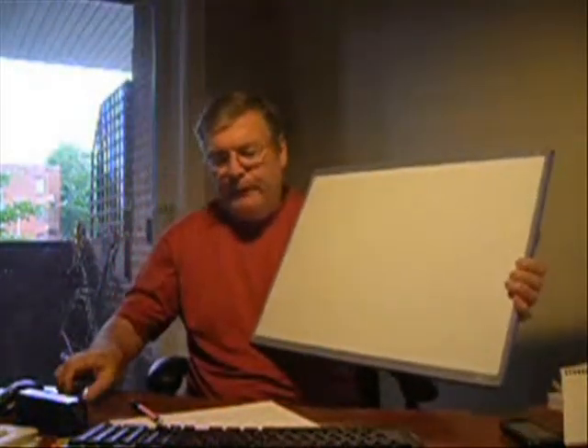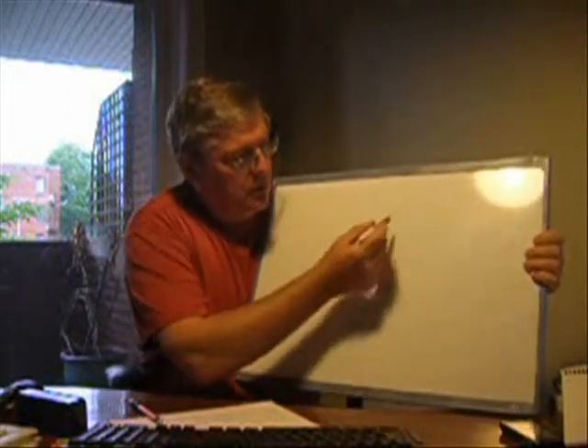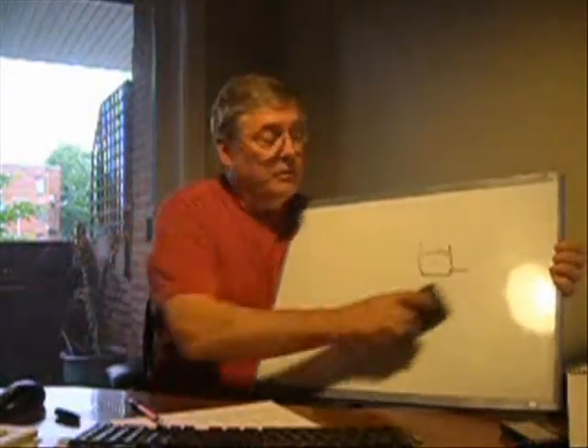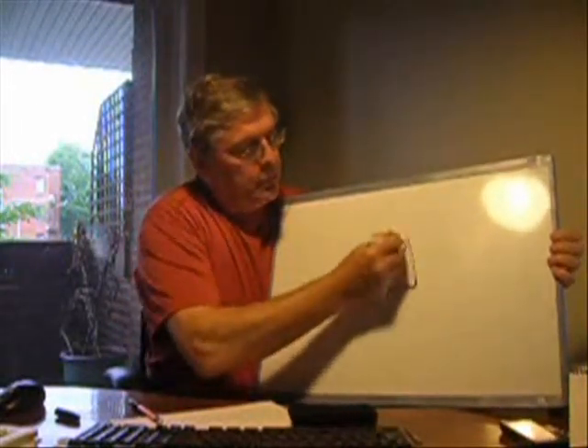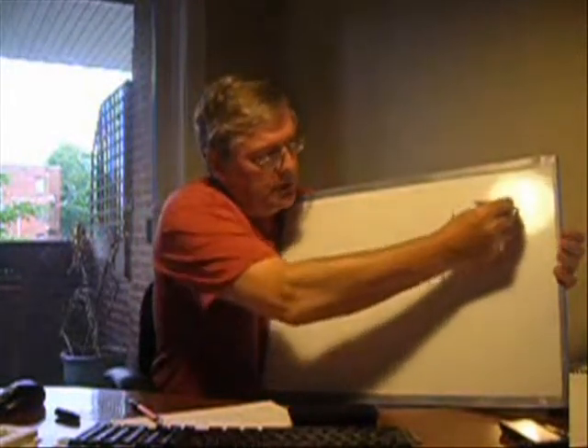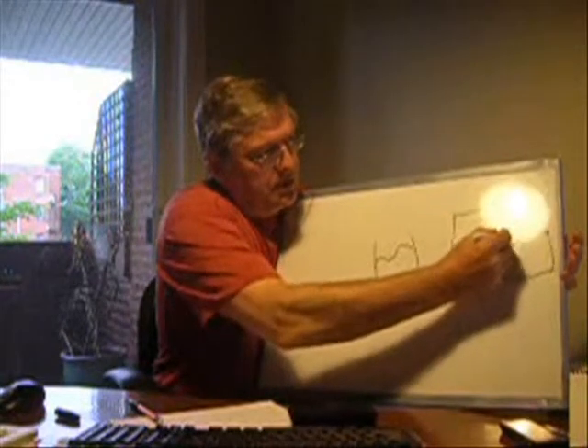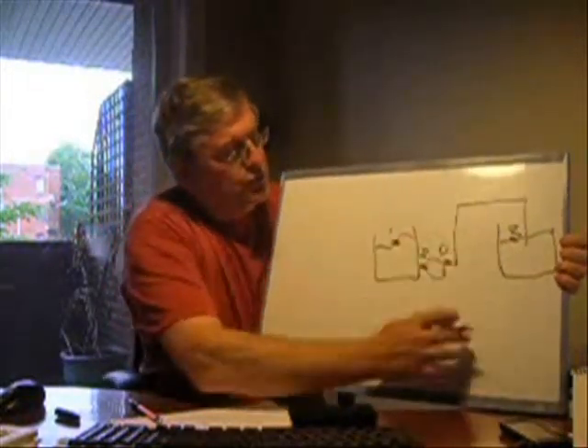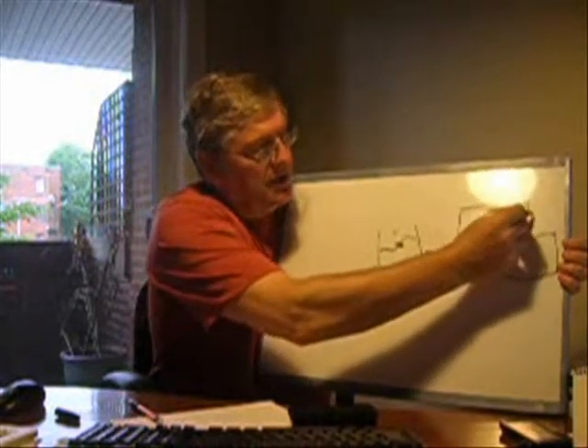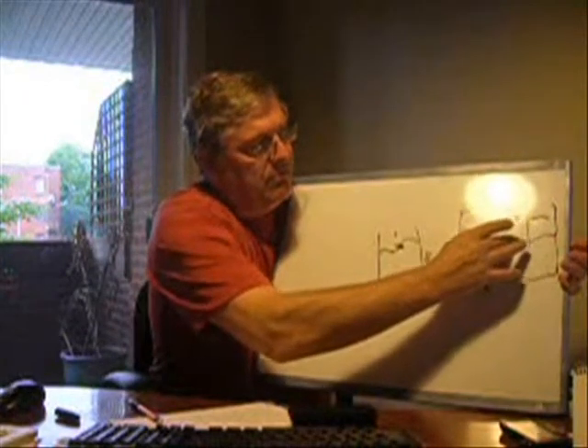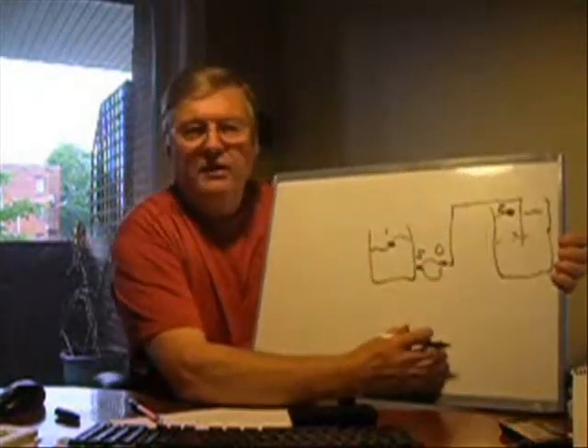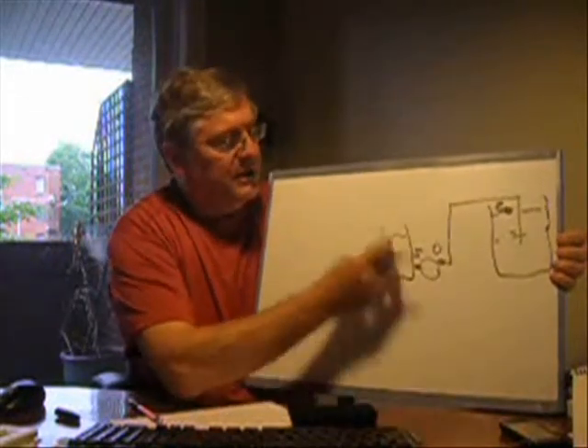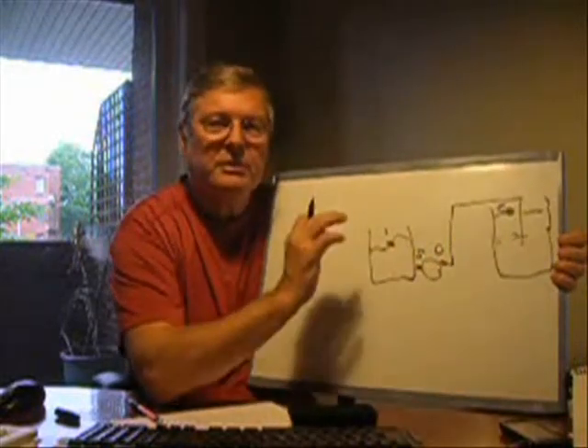Let's go back to the first video where I'll draw again a little schematic of a pump. We're pumping into another tank and we have points 2, S, D, and 1 — so we're pumping from 1 to 2, and usually 2 is going to be a little bit higher than 1. We have these two points of interest, S and D, and what we want is the difference in pressure between these two points — that's what the pump has to supply.